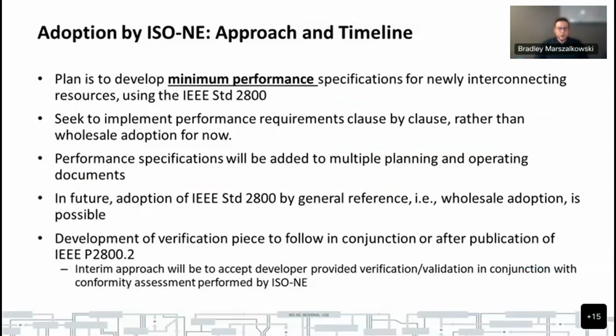So our plan here is to use IEEE 2800 to develop a minimum performance specification for newly interconnecting inverter-based resources. So it'll be applicable to Type 3s, Type 4 turbines, battery energy storage systems, solar, VSC HVDC, or really any converter-based resource. These minimum performance specifications will include the items within the standard that we feel support bulk system reliability, and we'll focus on the ones that are really critical for bulk system reliability. These are specifications and capabilities relating to things like ride-through requirements for RMS and instantaneous voltage excursions and frequency excursions, plant responses to disturbances like active and reactive power control, protective functions like rate-of-change-of-frequency, momentary cessation, and some other capabilities, possibly like fast frequency response or power factor capability.